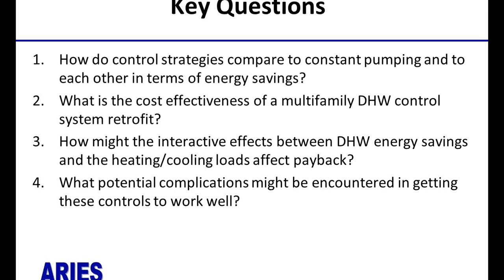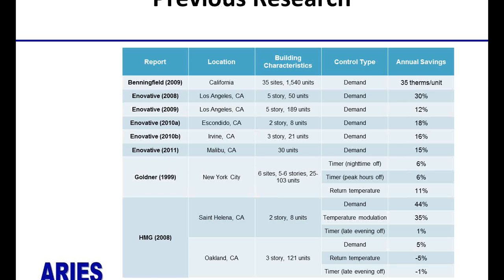And we wanted to also estimate and include the interactive effects between the DHW energy savings and the heating and cooling loads that we'll talk about in a little bit, and how that might diminish payback somewhat or not. Finally, the potential complications, we were hoping to identify and resolve in doing these installations and in testing these controls, any kind of problems that would occur to make sure that they're working well. So previous research, there's a good spread of energy savings attributed to the controls, and they generally range around 10–20%, with some higher than that.